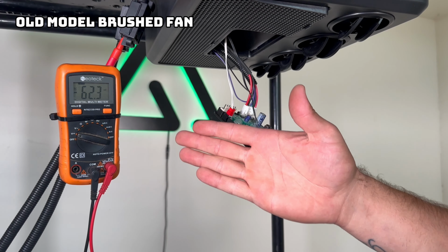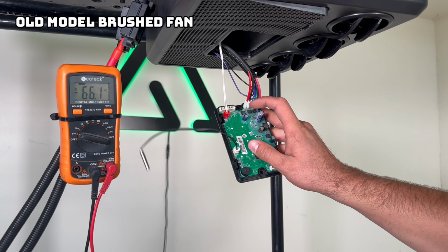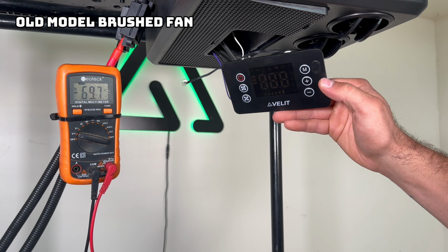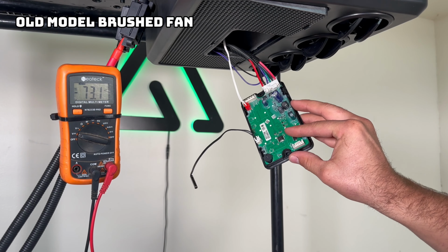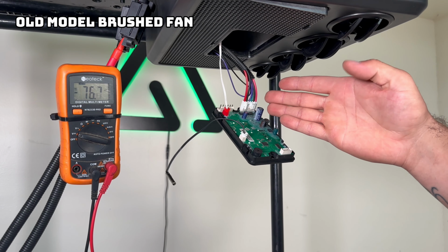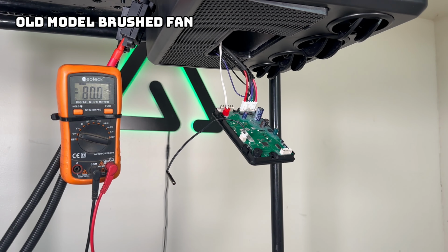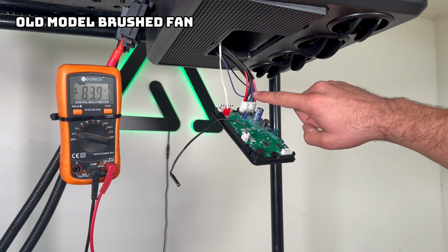While performing this test, if you don't get any voltage reading at these pins, it's likely a faulty control panel and you'll need to replace the entire board. If you do have voltage here, we'll need to go up top and take a look at the fuse that's in line along these wires.